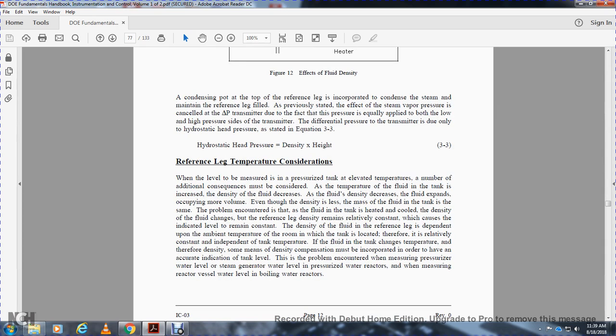Reference leg temperature considerations: when measuring the level of a pressurized tank at elevated temperature, additional consequences must be considered. As the temperature of the fluid in the tank increases, the fluid density decreases, and the fluid expands, occupying more volume, even though the density is less. The mass of the fluid in the tank is the same. The problem encountered is that when the fluid in the tank is heated, the density of the fluid in the reference leg remains relatively constant, which causes the indicated level to remain constant.